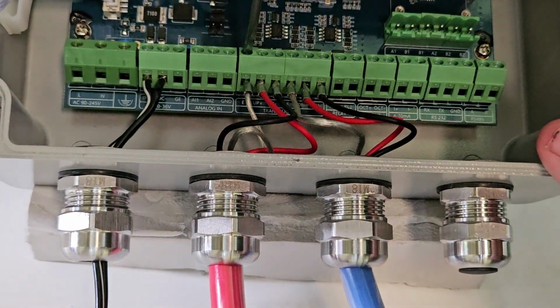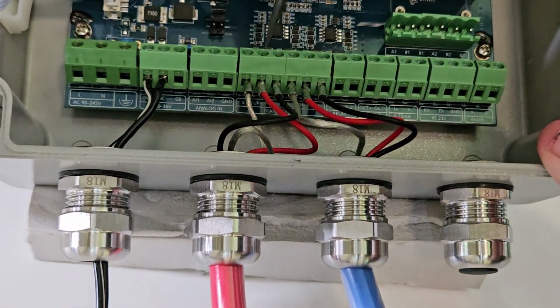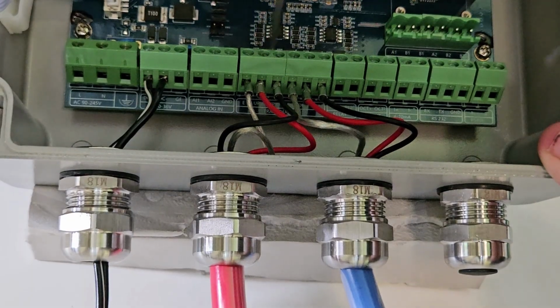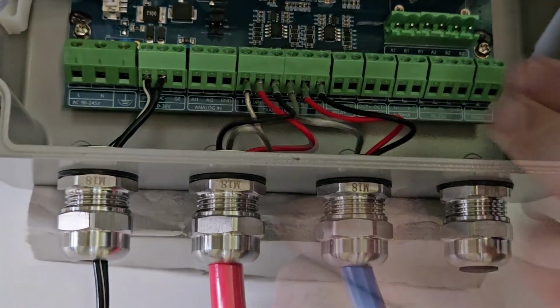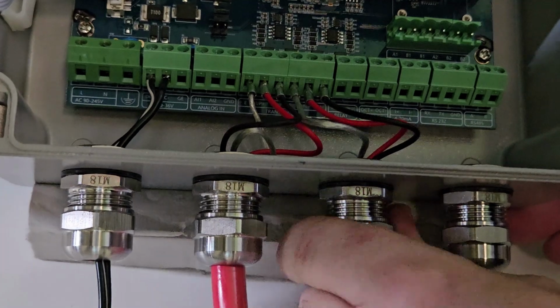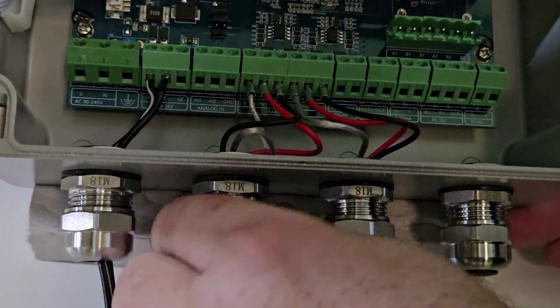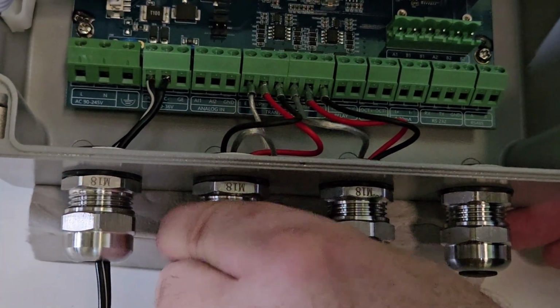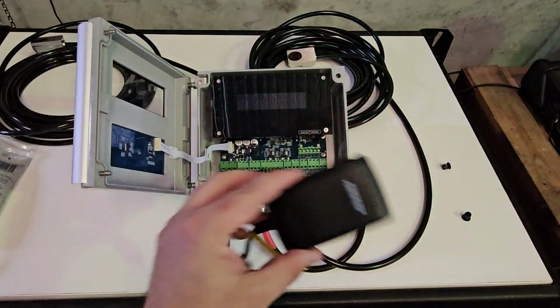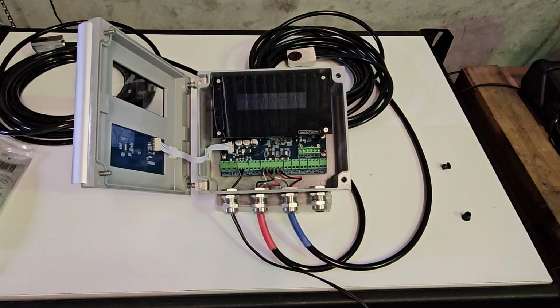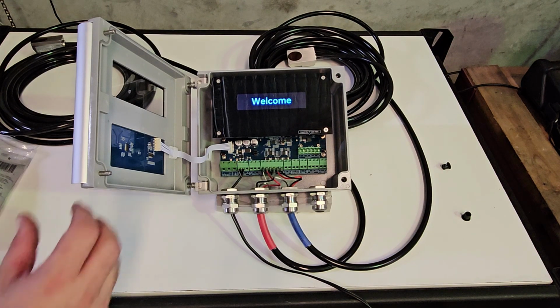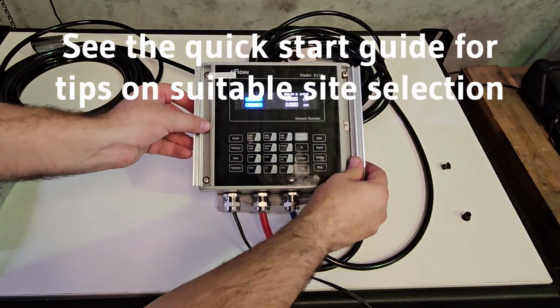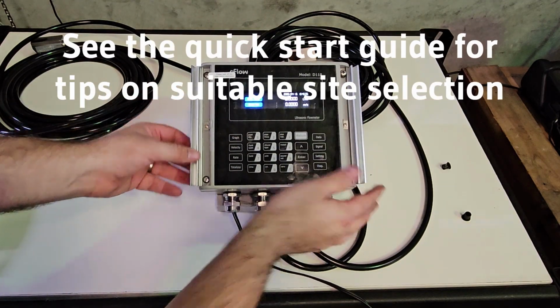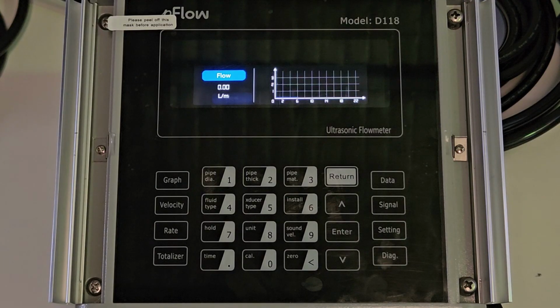Now tighten all of the screws for these wires and ensure none of them are touching and the wires are tightly held. Now you can tighten down the cable glands. This will help prevent water and dust ingress. Use a wrench if required. Now you can connect the power. I have plugged in the DC power supply. The flow meter will turn on as soon as power is connected. Shut the hinged cover so you can access the keys and see the screen. Now you can begin setting parameters.